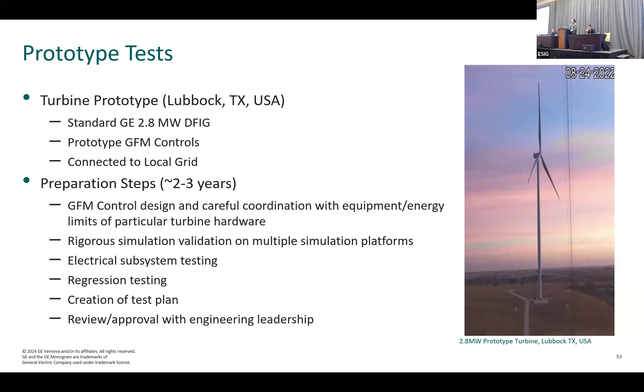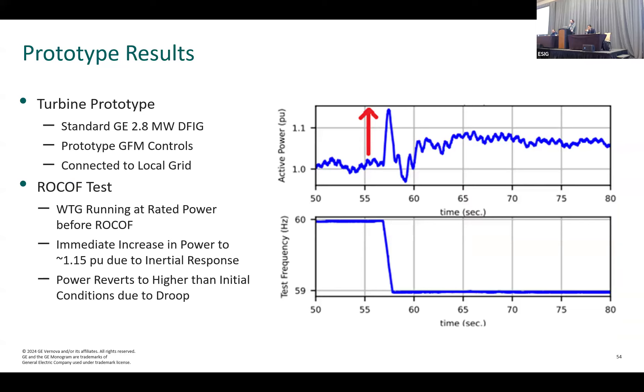After that was done, we created a test plan and brought it for review of engineering leadership, going into a lot of detail — dotting all I's and crossing all T's, going very rigorously. Some results at the top — this is actual measured results from the prototype site. This is a RoCoF test. The turbine is running at around one per unit power, then we add a RoCoF signal — an artificial frequency signal, since we cannot bring the real grid frequency down. We compared this signal input against detailed simulations to get the right response.